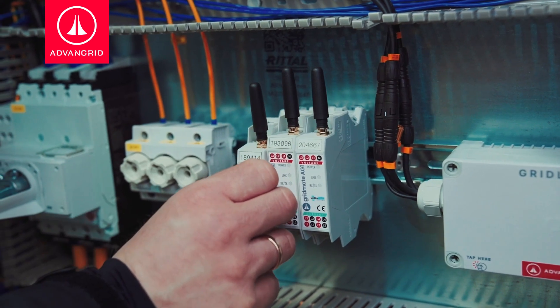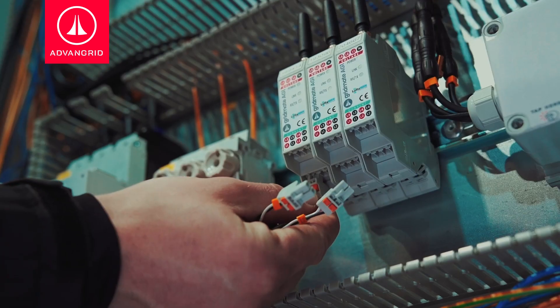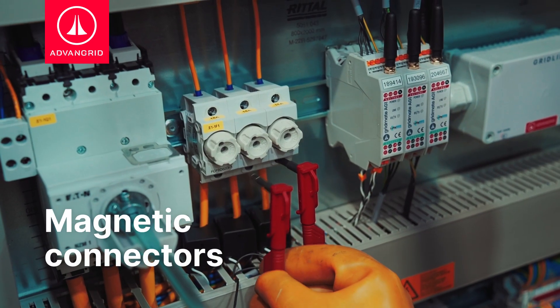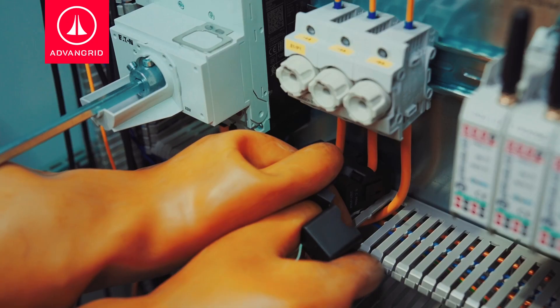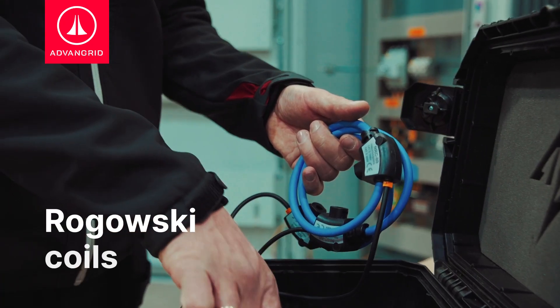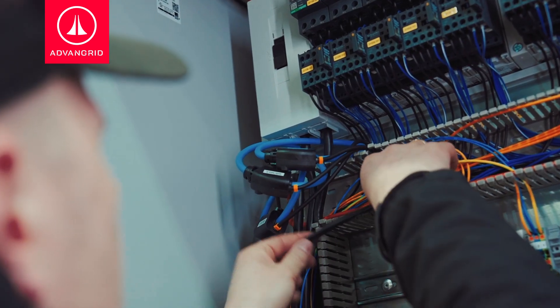The installation process is straightforward. The sensors are clipped on the DIN rail in the electrical distribution box. The wires that come out of the bottom of the sensor are for voltage readings, and they can be connected using magnetic connectors or alligator clamps, or wires can be screwed straight to the switch. The wires that come up from the top of the sensor are for current readings. We use Rogowski coils or split-core current transformers that are opened and clipped on the wires for current measurements.